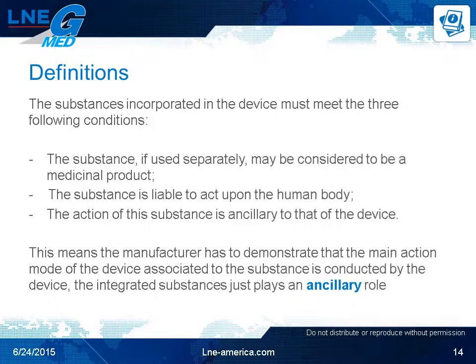Again, all these three conditions should be met in order to consider the device a combination medical device, and this leads to a critical point the manufacturer should consider. The manufacturer has to demonstrate that the main mode of action of the device associated with the substance is conducted by the device. The integrated substance just plays an ancillary role in the function of the device.